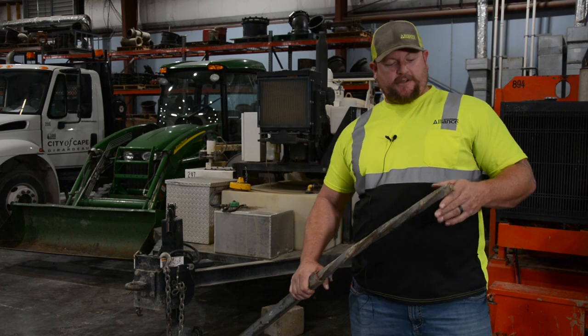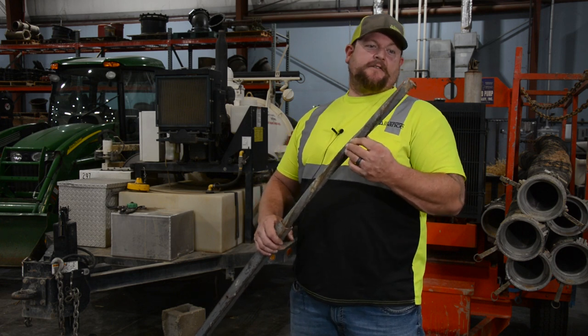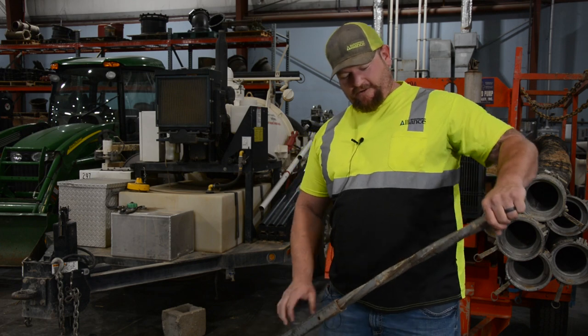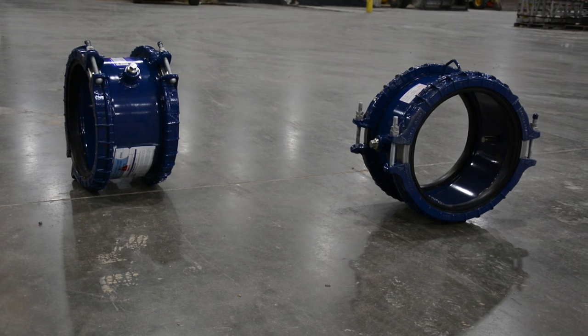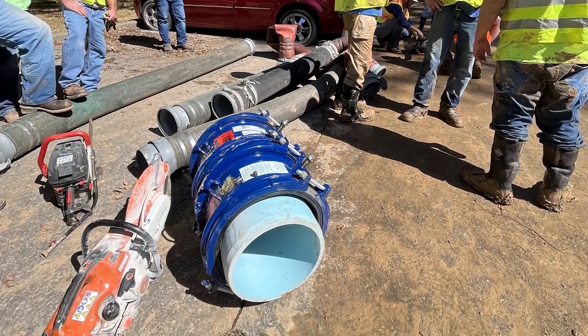This is one of the valve wrenches that we used. I didn't do this by myself — there were a couple of guys helping me turn, and we thought we were turning the valve but as you can tell we were turning the wrench, not the valve. So it kind of gave way after we turned it quite a few times. Those are Hymax fittings. There was a piece of the main that had to be cut out, so they're used on each end as a dresser sleeve. You cut a piece of main out, put one on each end and tighten them back up.